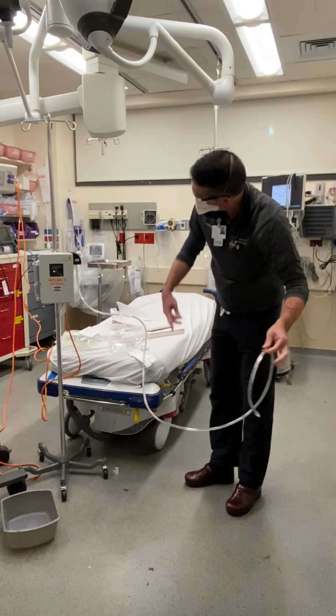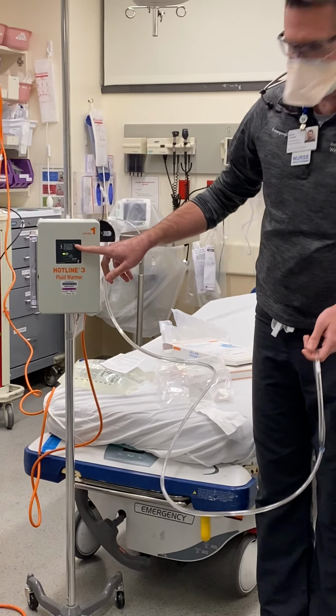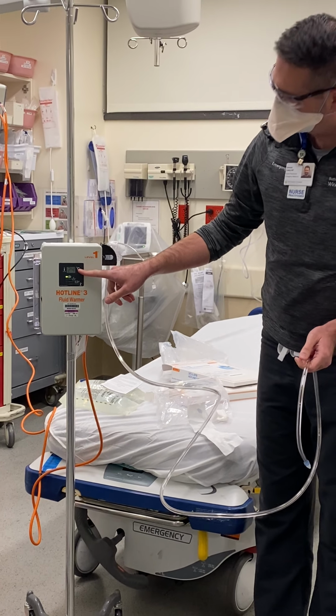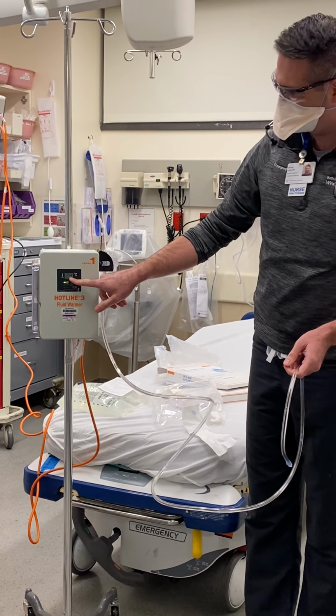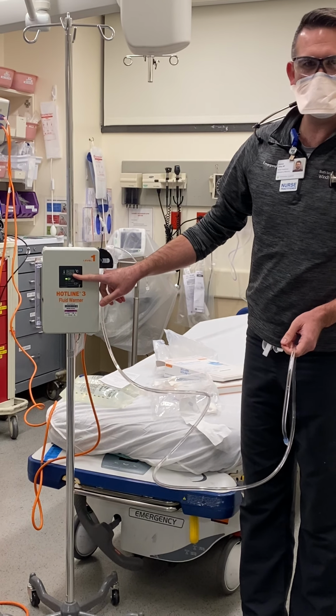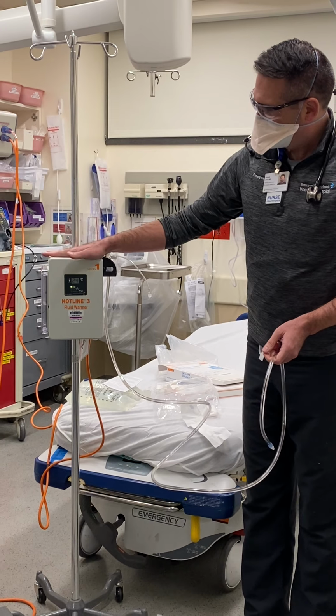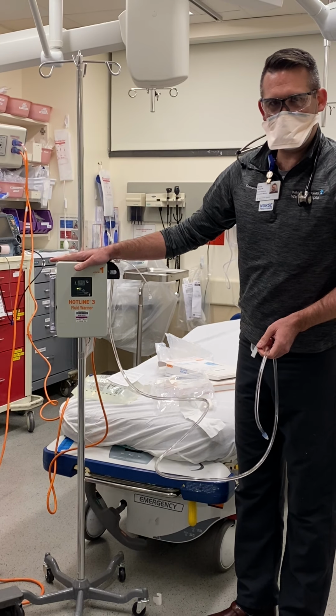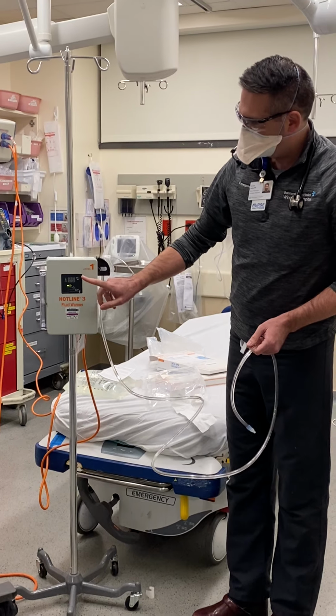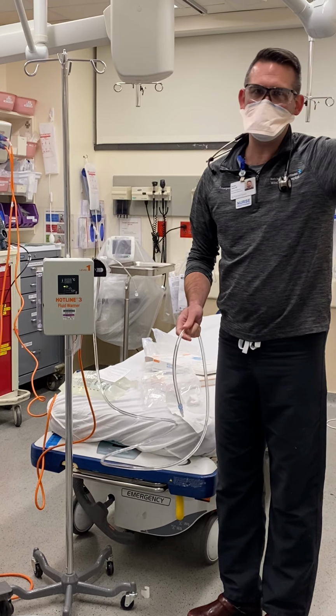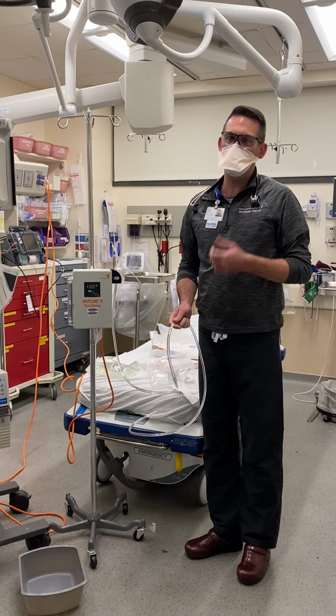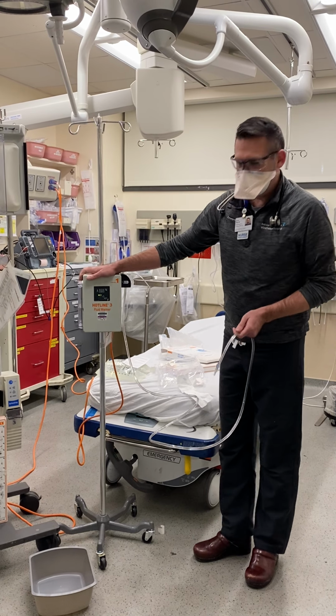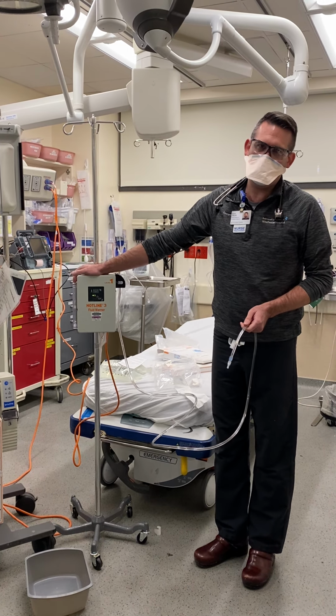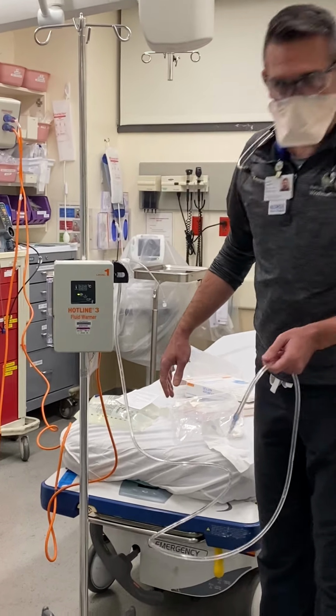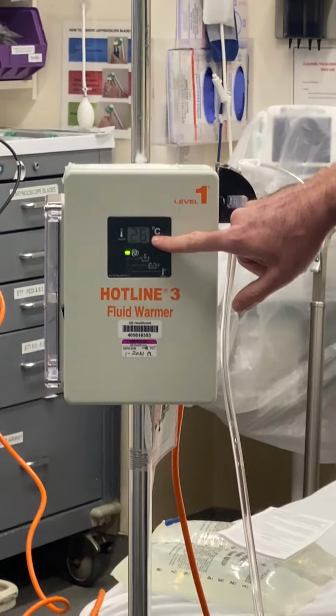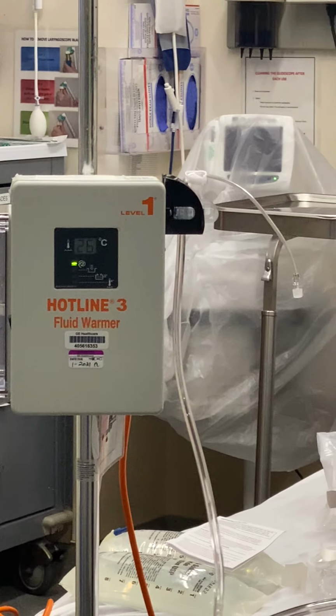Doing it now. One thing to keep in mind is this is the current temperature of the fluid inside the fluid warmer, and that's at 24 centigrade. So that's just a little bit above 76 degrees Fahrenheit. Now, this will warm it to just about 40 degrees centigrade, which is above body temperature. So if you store these devices out in the ambulance bay entrance where it's very cold in the wintertime, this will keep it very cold and it will take very long to heat up. And if you'll notice, even in the time that we've been talking, the temperature already reads 26 degrees centigrade, and I can feel this warming up.